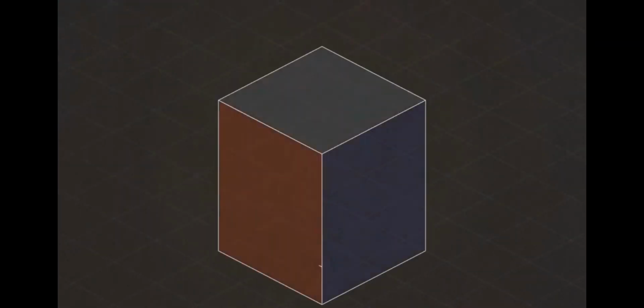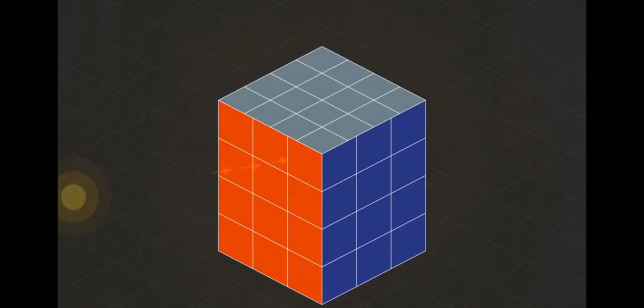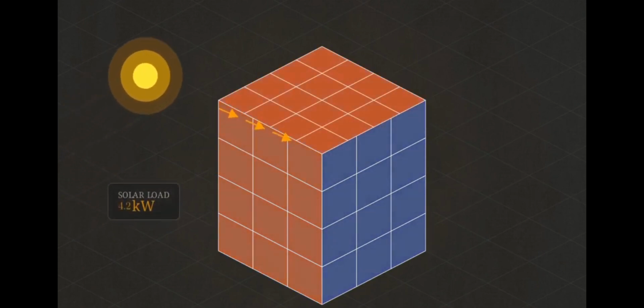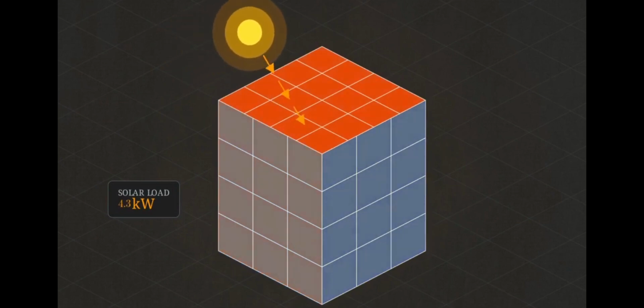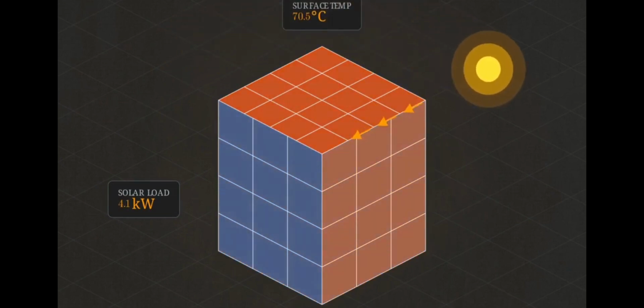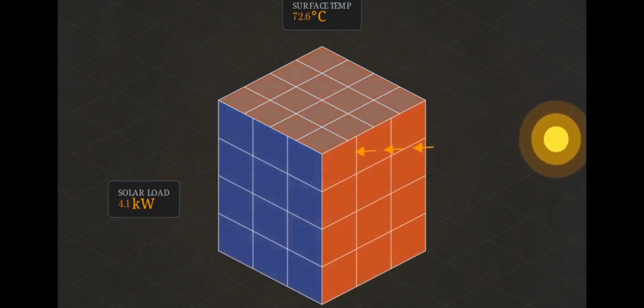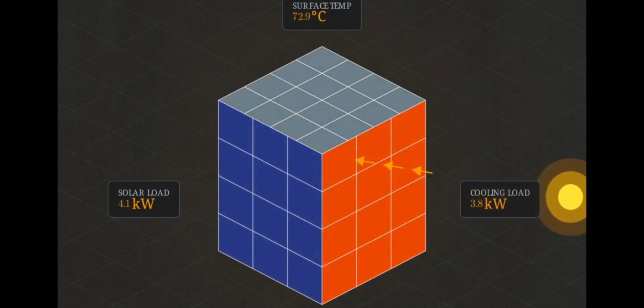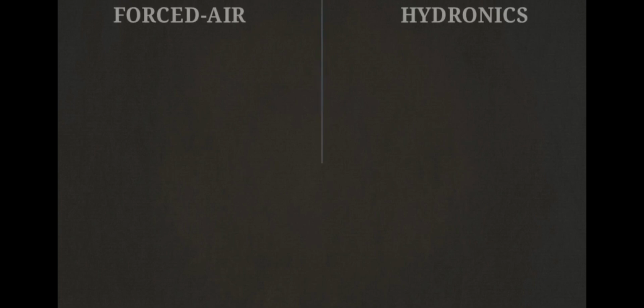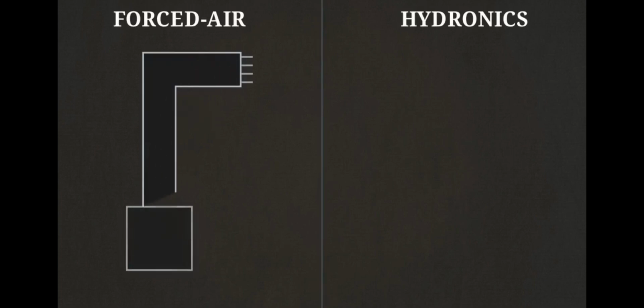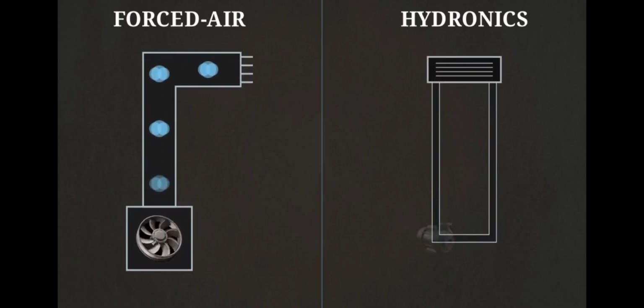Think about a building like a giant cube under the sun. Heat is constantly pushing its way inside through the walls. This is the solar load. To keep things comfortable, your cooling system has to match that heat load exactly. It has to scoop that exact amount of energy up and throw it out. But how do we actually move that thermal energy around? You usually have two choices: forced air or hydronics. Forced air uses a massive fan to push conditioned air through large ducts. Hydronics uses a small pump to circulate water through tight pipes. Water holds way more heat than air, making hydronics incredibly efficient.